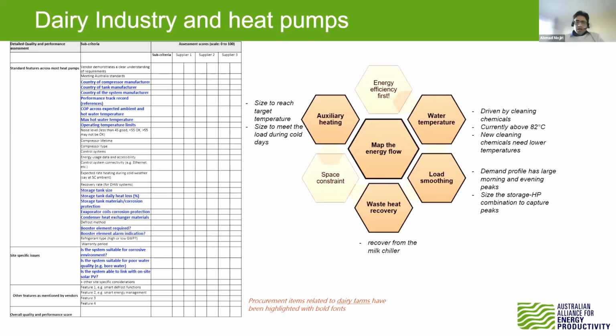Sure. The way we're capturing the important lessons you guys learned in our guidance report is by emphasizing that understanding the energy flow is a central part. Most of your talk, Mario and Greg, was about water temperature and how it affects the entire design. We cover that in the report, highlighting the maximum temperatures required, thermal storage design, selection and integration with the heat pump to maximize utilization and reduce running costs. You mentioned something important - minimizing the duration hot water remains in the tank to reduce heat losses. We've addressed that heat loss aspect of storage systems in our document.